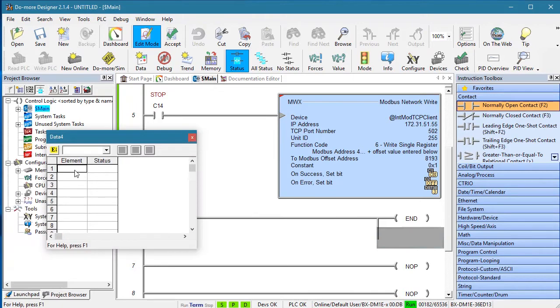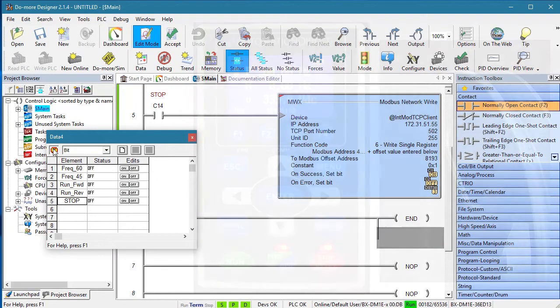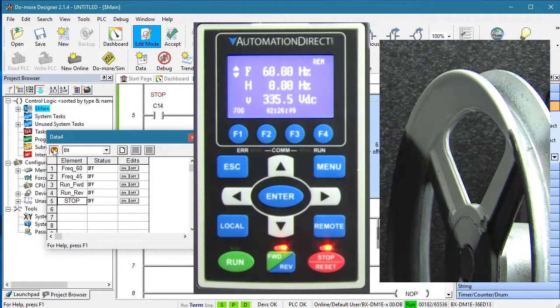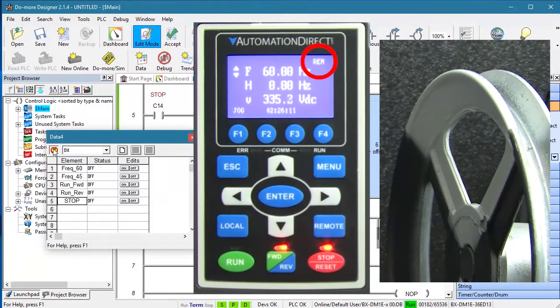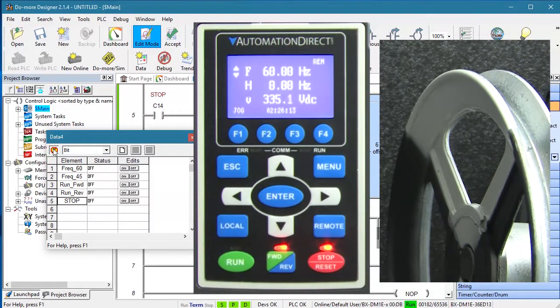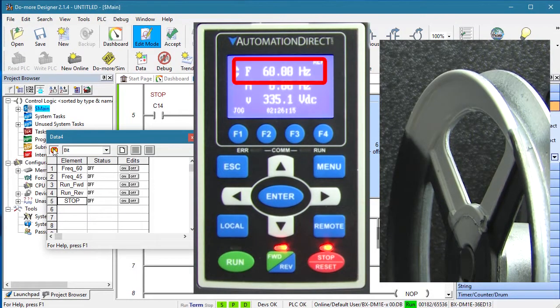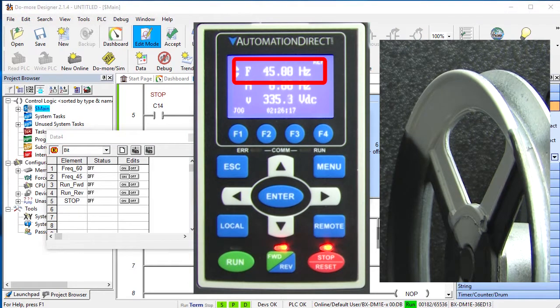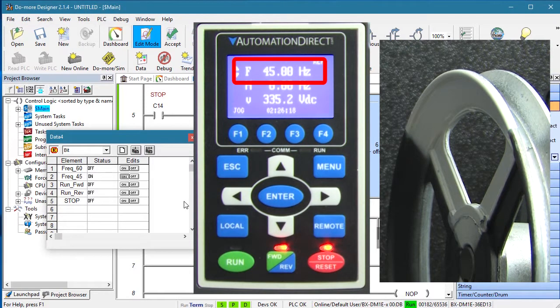Let's bring up a data view and add those control bits. The drive is configured for Modbus TCP and it's in remote mode so it's ready to go. The PLC is running so if we activate the 45 Hz instruction, sure enough the drive changes frequency.